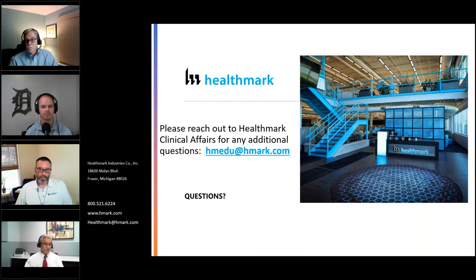I am following AAMI standards and other recommendations. Why do I need to use manufacturer IFUs? As we mentioned, the IFU is really the only one that is supposed to be validated. We look at this as a validated IFU to be clear. That's important because, for example, CMS and organizations like JCO require you to go by that, because that is the manufacturer's process, validated based on that IFU. Although sometimes those IFUs, if not validated, aren't as effective.